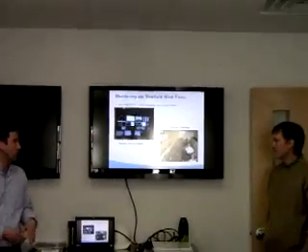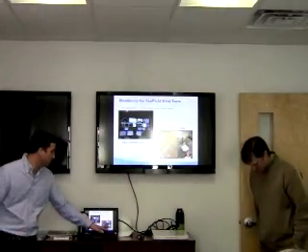So these guys, they have real-time control. They notify us in real time of any issues, concerns, a fuse goes. We have icing. We need to know what we need to do. We have different operating procedures for icing and stuff like that to keep down the wear and tear of the machines and things of that nature. Curtailments that come in from the ISO New England, regulatory curtailments to the site, or curtailments from the other utilities that we supply to. Those are all sent in real time, and the monitoring is real time.